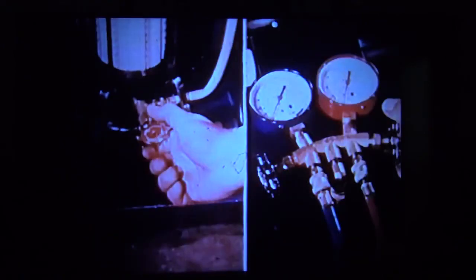system is operating. When the system is fully charged, close the bottom valve on the charging cylinder and the manifold discharge valve. Slowly loosen the hose connection at the bottom valve on the charging cylinder and allow the refrigerant pressure to bleed off. Then disconnect the hose from the valve.